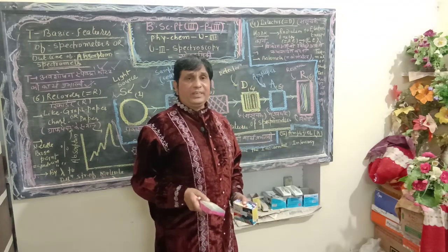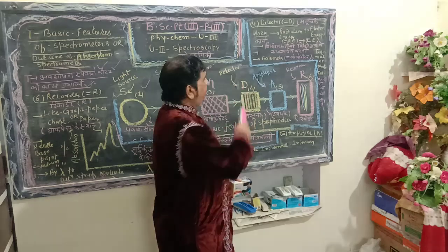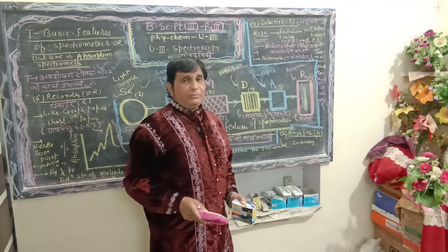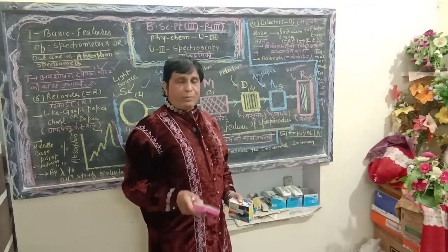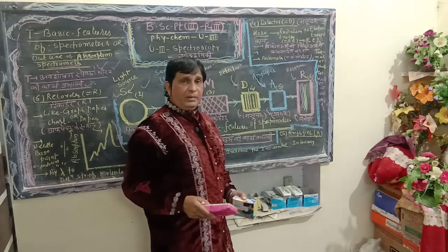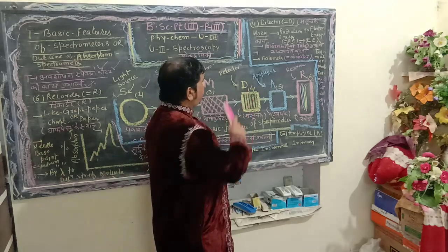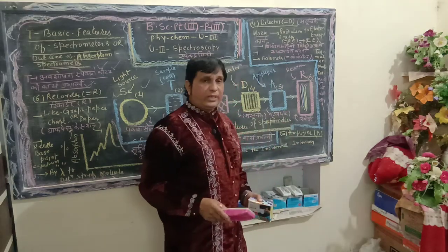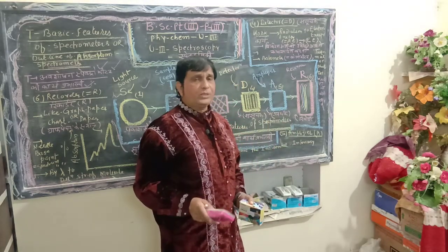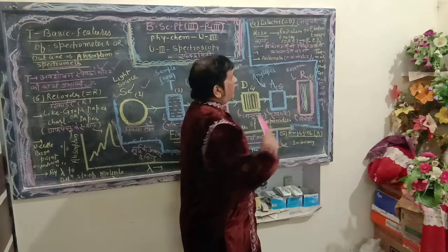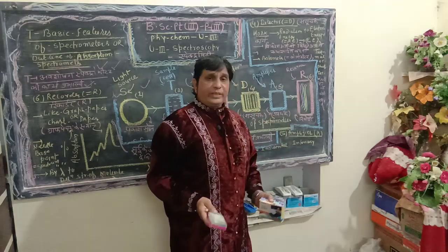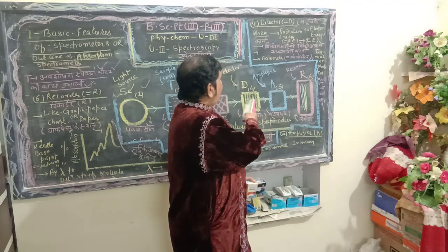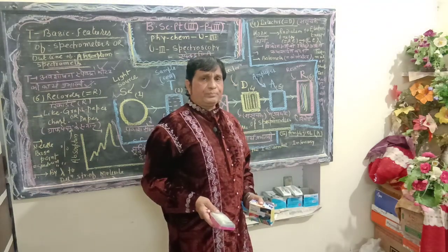Once again, try to understand the main function of the detector here, which is connected to the monochromator M. The transmitted radiation is now allowed to pass into the detector. The main function of the detector, part 4, is the conversion of radiation energy to electric energy. For this purpose, a bolometer, thermal or photo detector can be used in the role of detector 4.